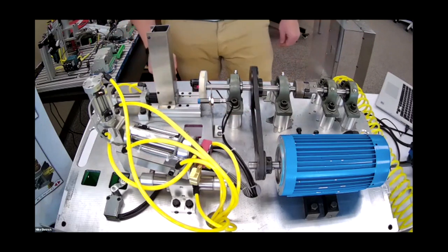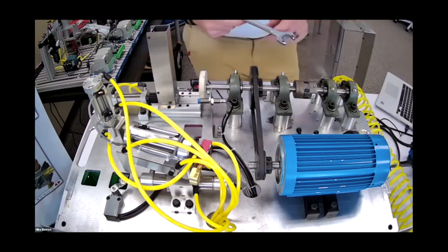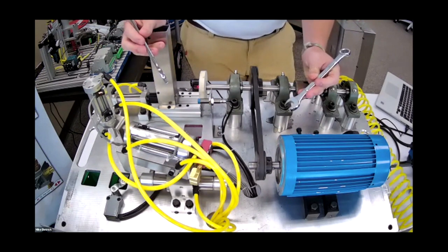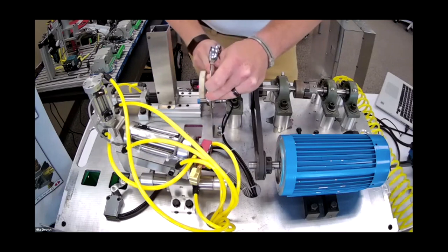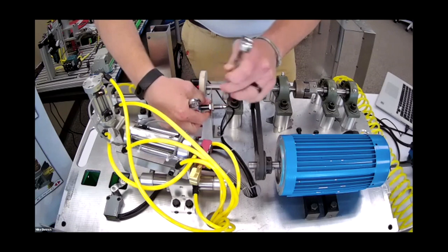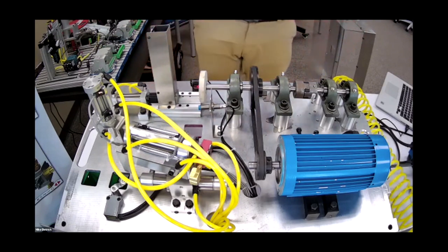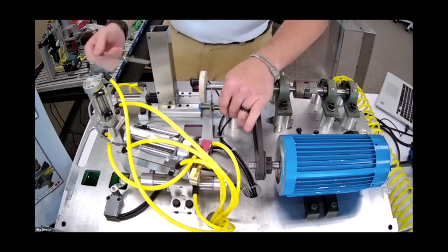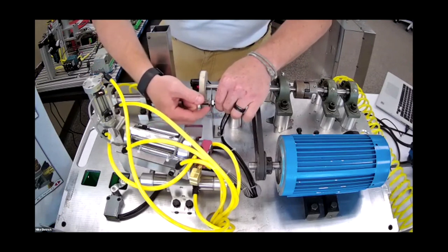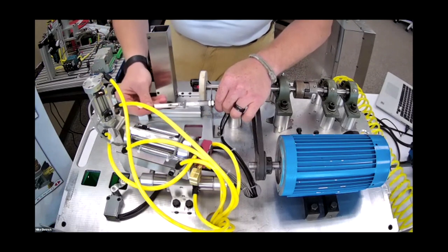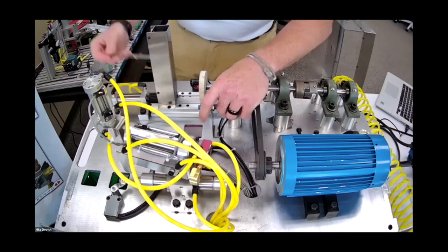All right, that's taken care of. What's next? Then grab the two 17 millimeter wrenches and my machinist rule. All right, good to go. I then want to loosen both nuts on the sides of the slots of the sensor, just enough so that I could bring it down to the bottom and begin adjusting it. All right, so I have the sensor all the way down to the bottom loosened up. What's my next step? So now I'm going to try and measure it out using the machinist rule. 25 millimeters, I believe, would be the right measurement to sense the block. So I'm going to go from the blue tip to the top of the nut and try and measure out 25 millimeters. All right, making that measurement now. Need a little bit more.